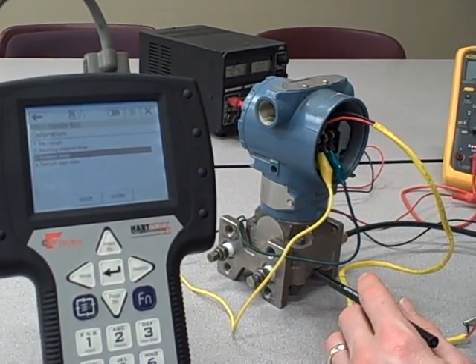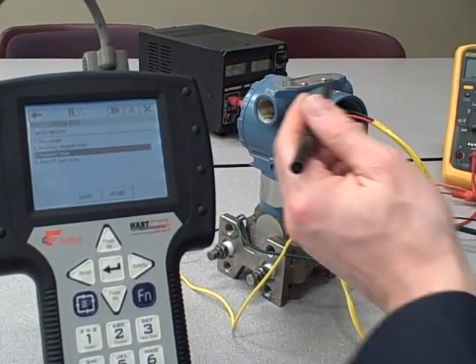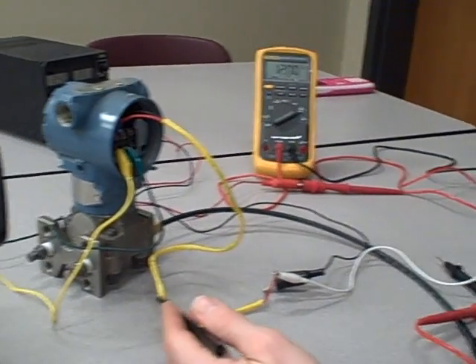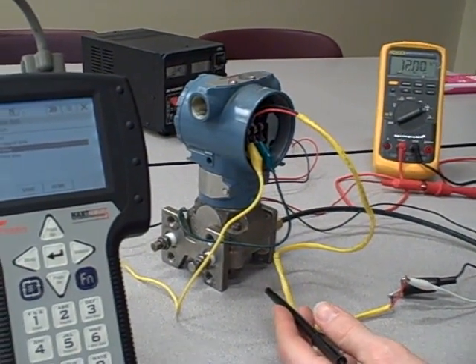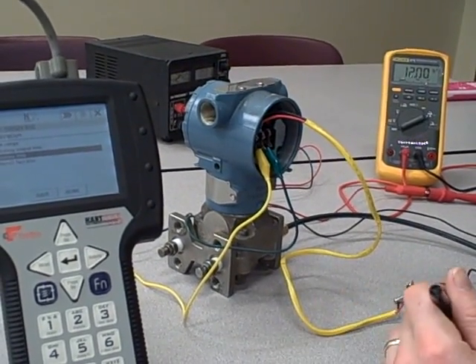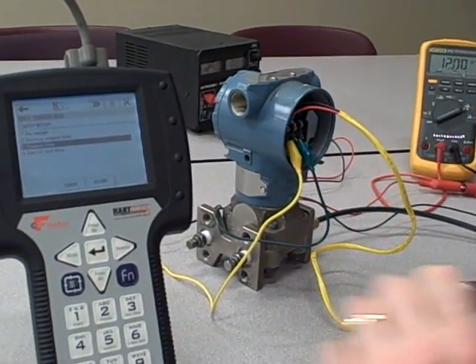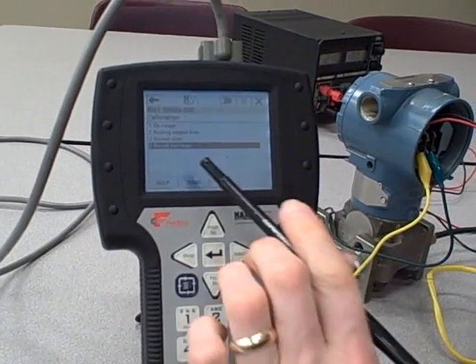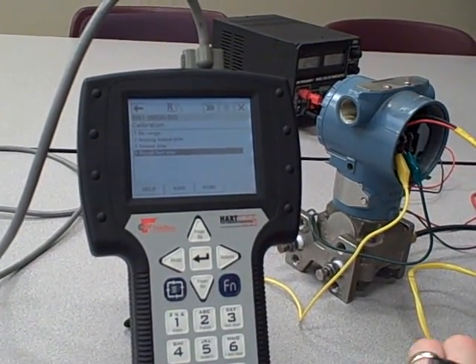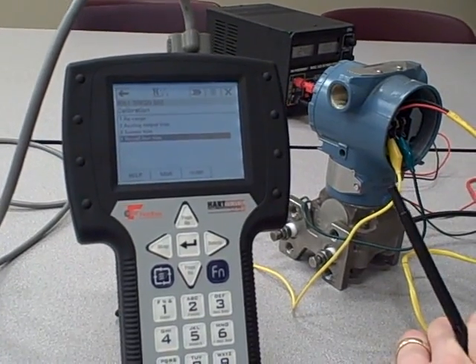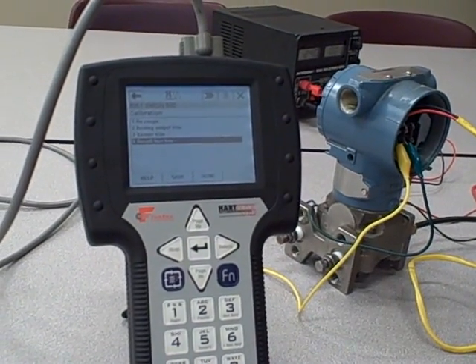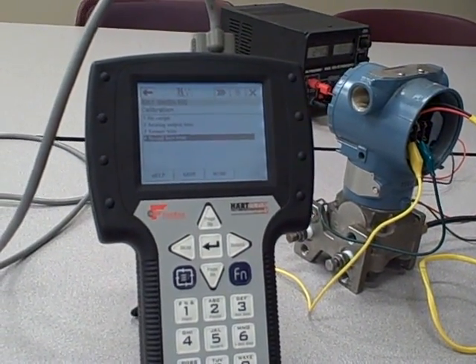In order to do a sensor trim, I would need, in addition to the transmitter and a source of pressure like this pump, some other independent pressure measuring instrument that I could use as a standard. I do not have that on this test bench, so I will not use that. I could also go into Recall Factory Trim, in case you think you've horribly messed up the trim setting values on the transmitter. You can recall the factory trim values that were set at the time of manufacture.